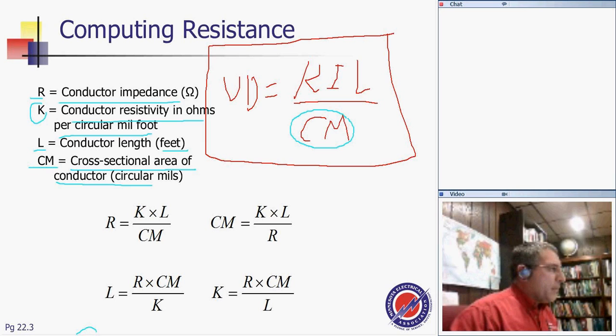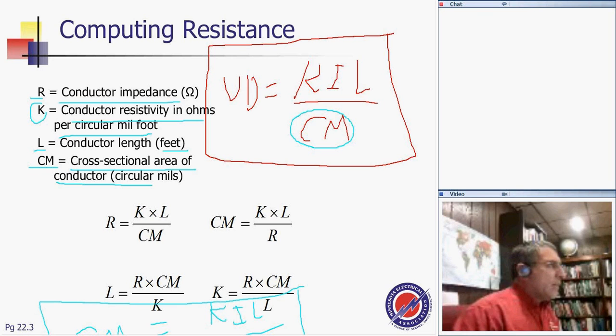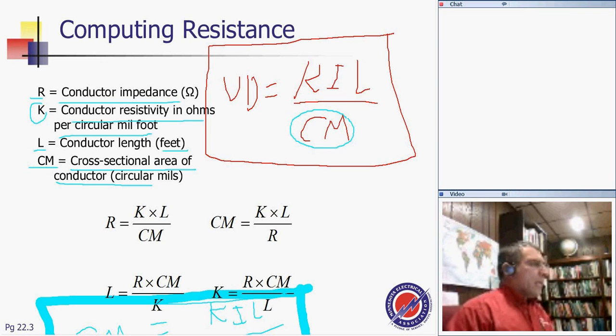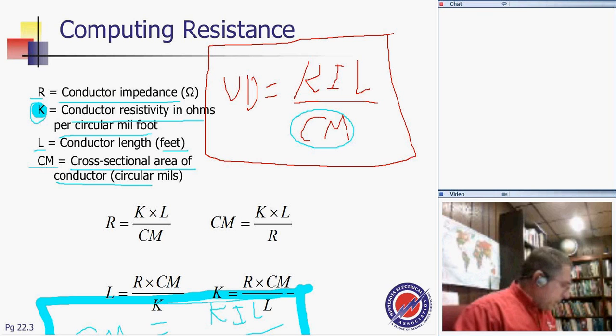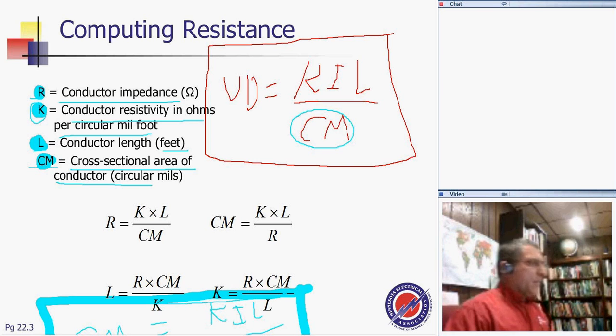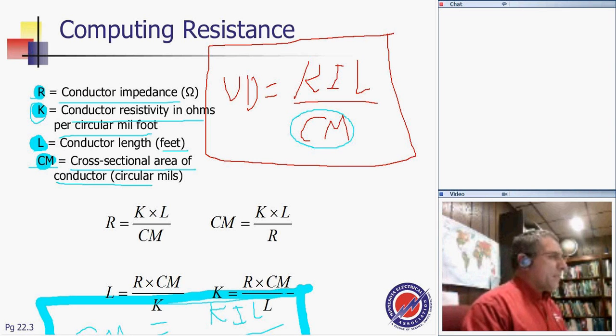I find the conductor. If I flip this formula, CM equals K I L over voltage drop, and we size conductors based on voltage drop. Exact formula. Then we size the conductor based on the voltage drop. If you look at the circular mil, K is the constant right here, then 10.4 for copper, or 12 ohm, or something, or 17 ohm. Circular mil is the cross-section area of the conductor, and R is not here, but if we have it, it's going to be the resistance. Anything, guys, about this formula? Any question about this formula? We'll take a few examples about it in a second.